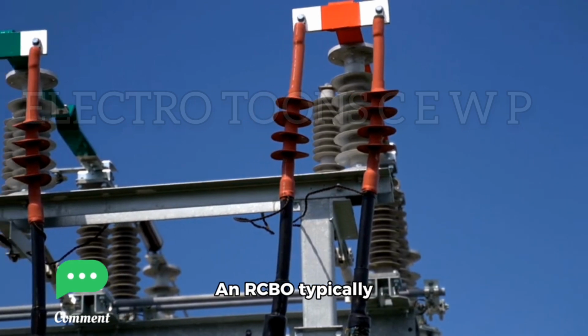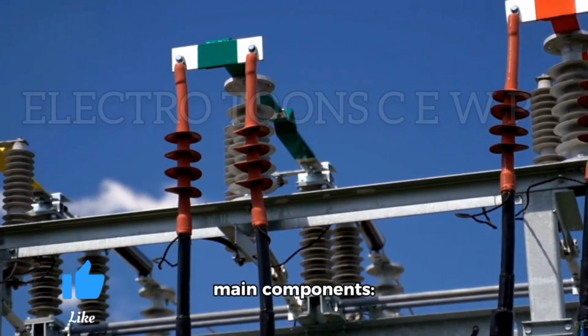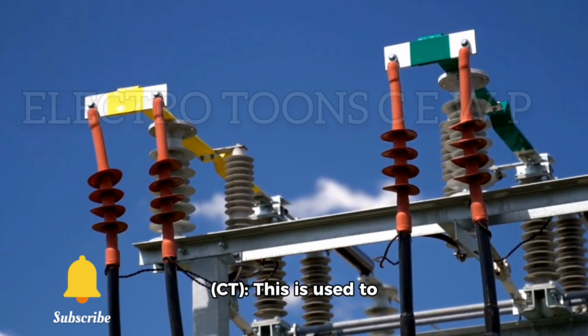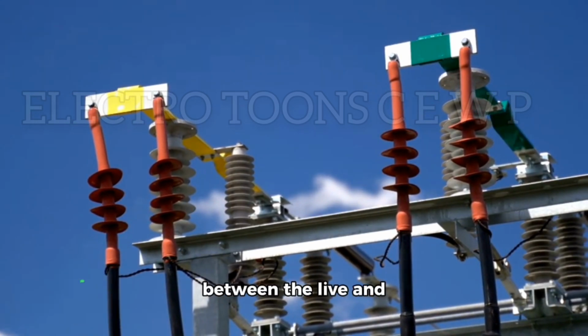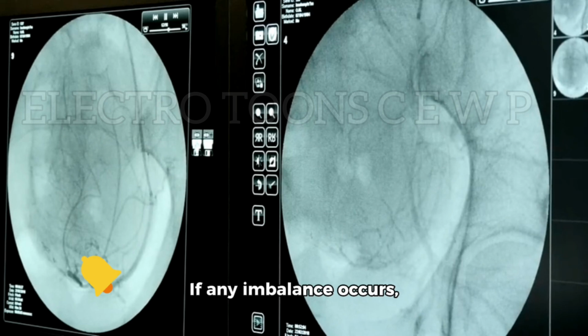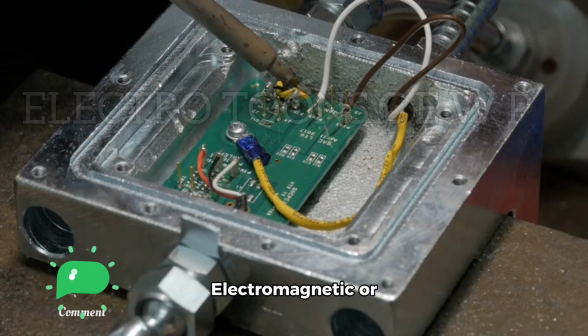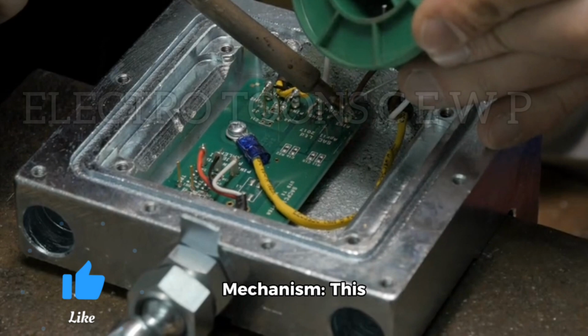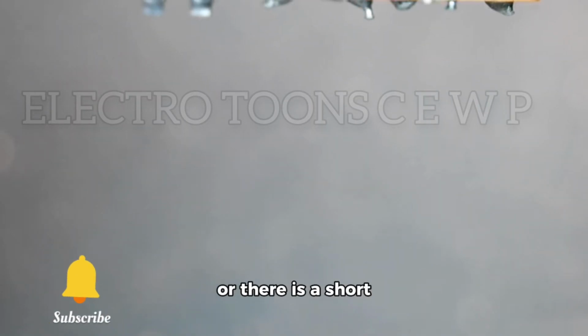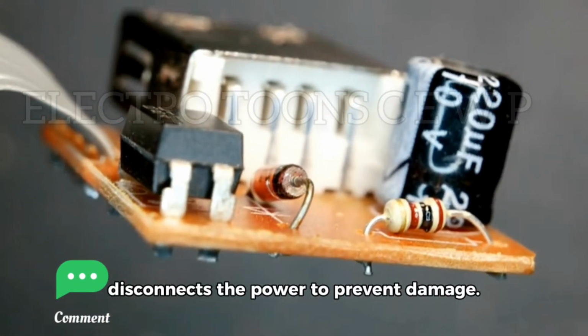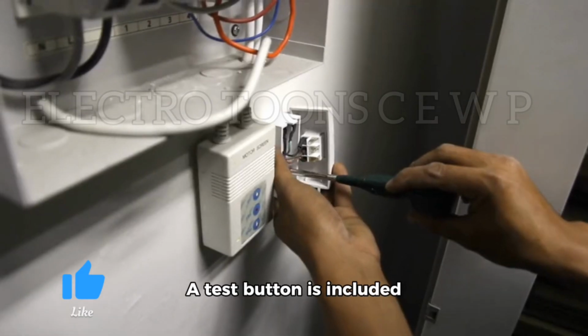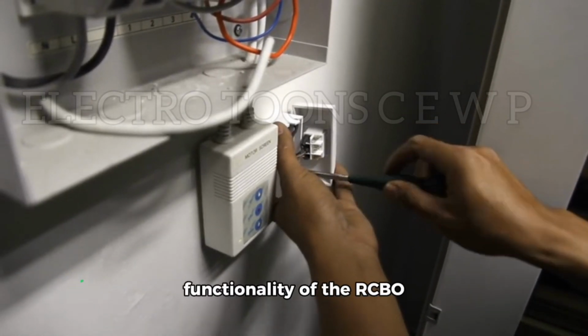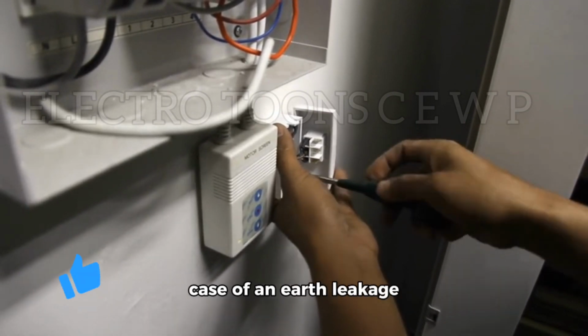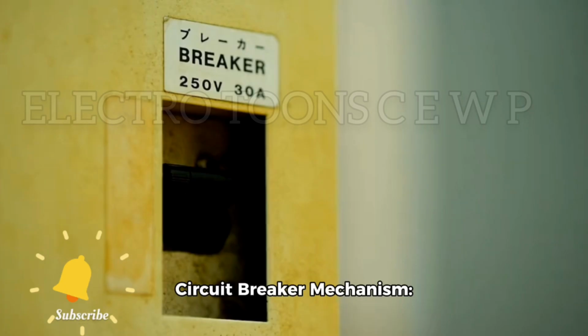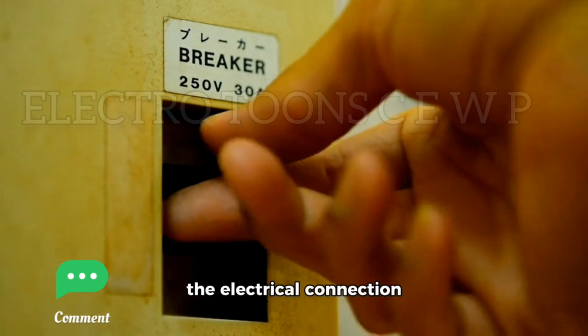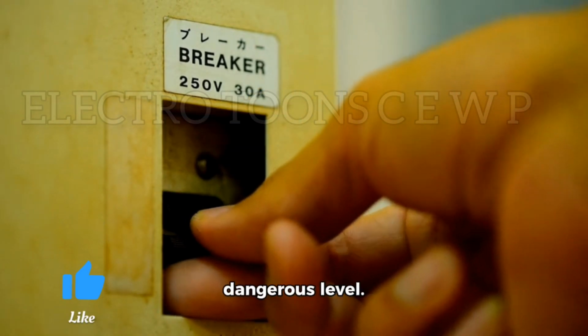An RCBO typically contains the following main components. Current transformer (CT): this is used to monitor the balance between the live and neutral currents. If any imbalance occurs, the CT detects it. Electromagnetic or thermal trip mechanism: this detects when the circuit is overloaded or there is a short circuit and disconnects the power to prevent damage. Test button: a test button is included to manually check the functionality of the RCBO to ensure it will trip in case of an earth leakage or overload. Circuit breaker mechanism: this physically interrupts the electrical connection when the current reaches a dangerous level.